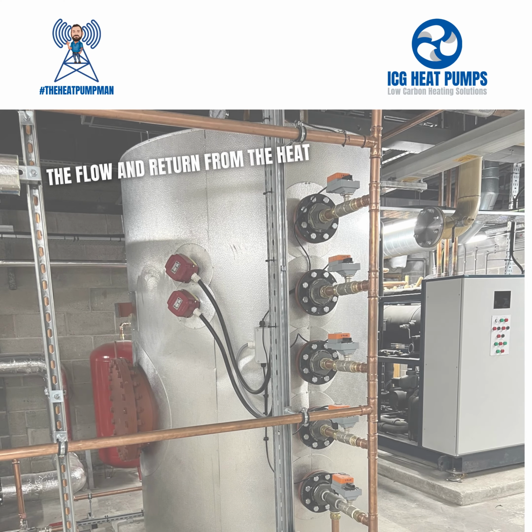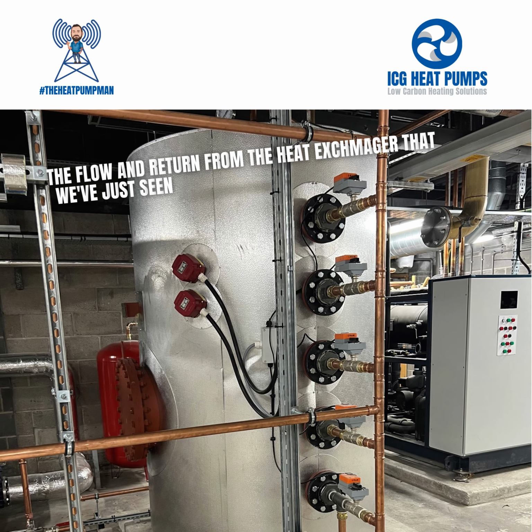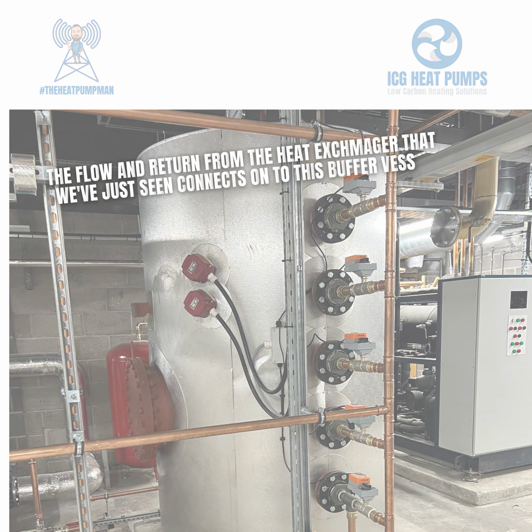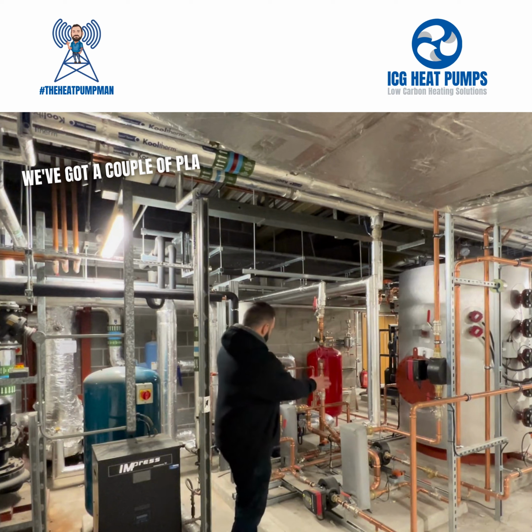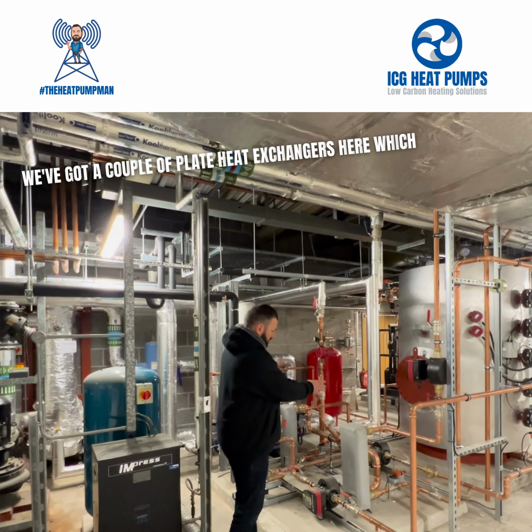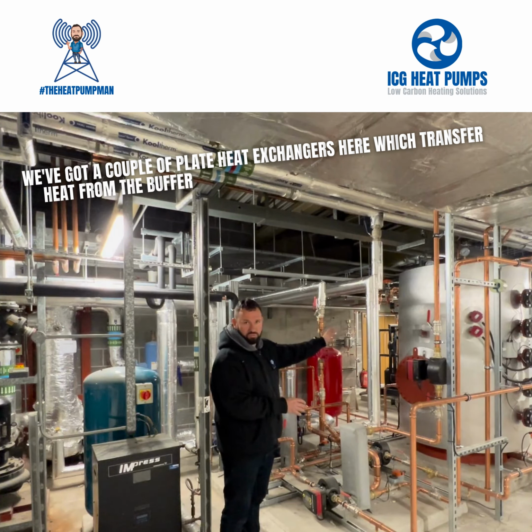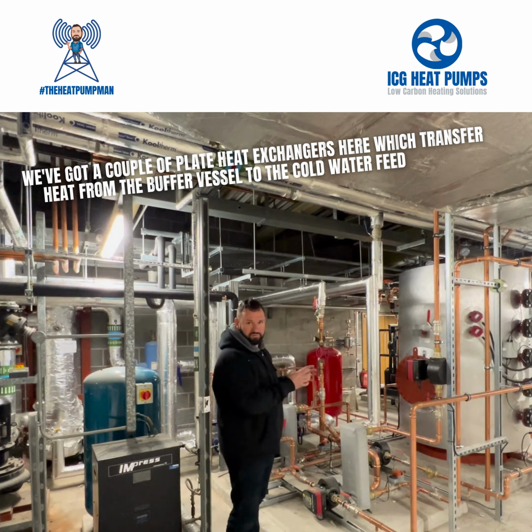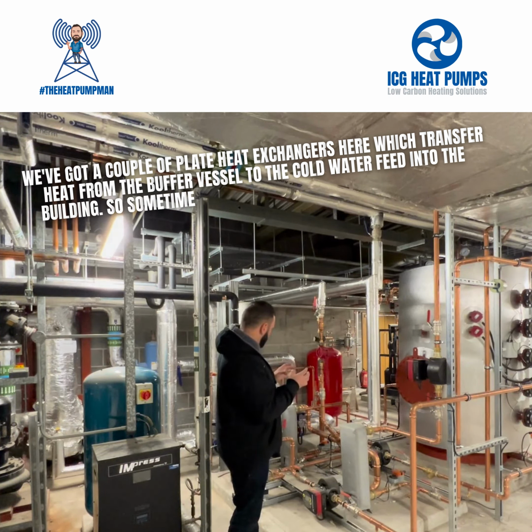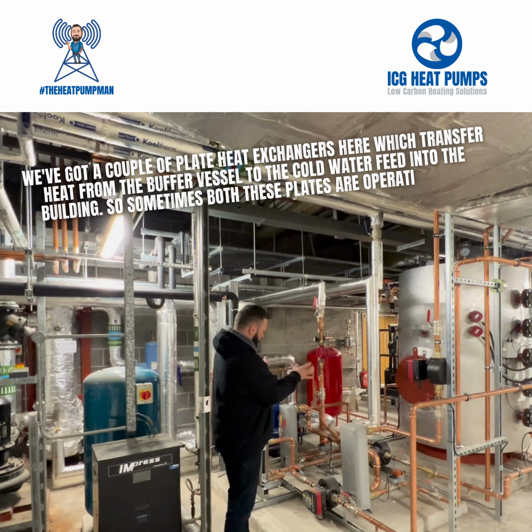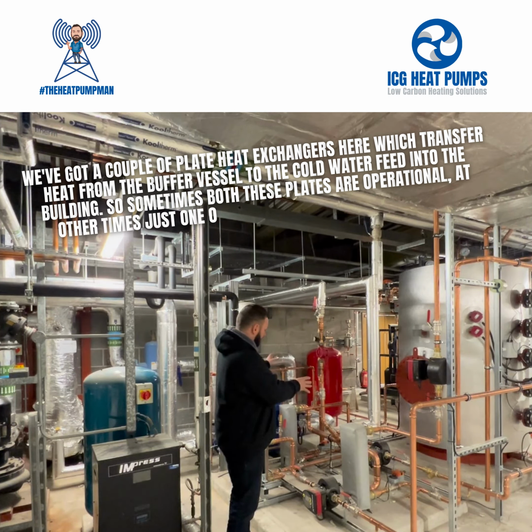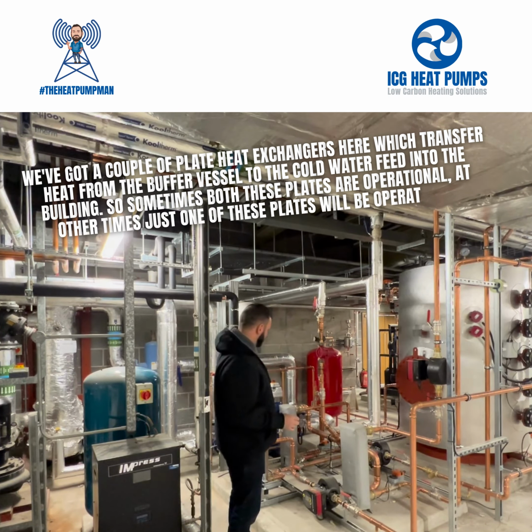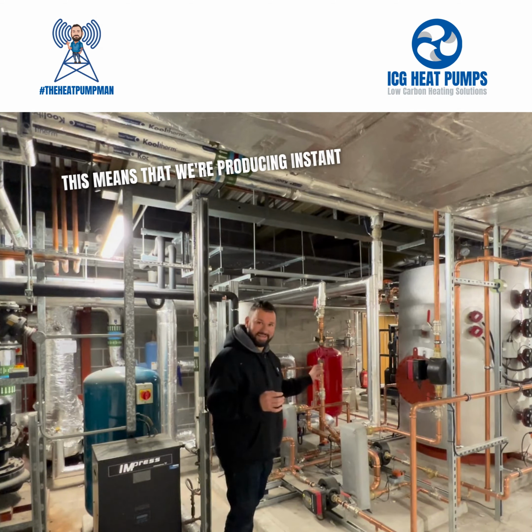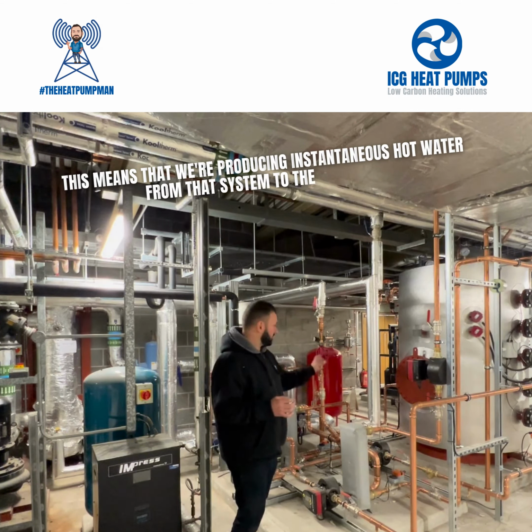The flow and return from the heat exchanger we've just seen connects onto this buffer vessel. We've got a couple of plate heat exchangers here which transfer heat from the buffer vessel to the cold water feed into the building. So sometimes both of these plates are operational, at other times just one of these plates will be operational. This means that we're producing instantaneous hot water from that system to the building.